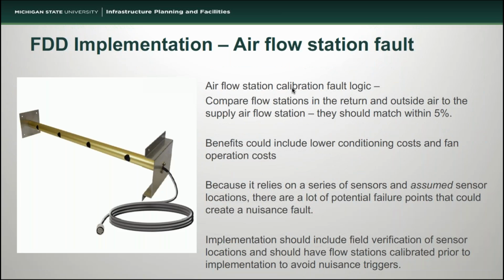A couple of other fault examples that we have. One of them is an airflow station calibration fault. So in an air handler, we'll measure the amount of air that's coming back from the space, the amount of air that we're bringing in from outside to help ventilate, and then the amount of air that we're sending back out to the space. So at any given time, you should be able to compare the amount of air that's coming back from the space and the amount of air that's coming in from outside, and they should pretty much match with how much air is being supplied into the space.